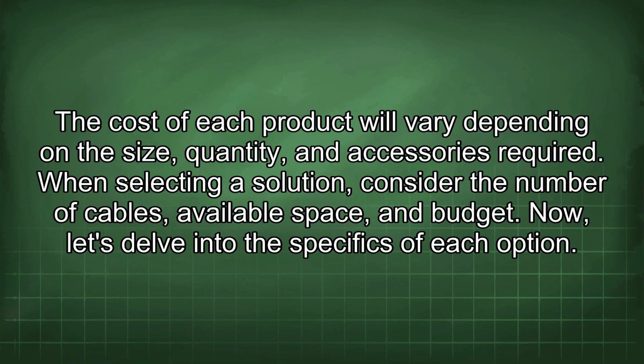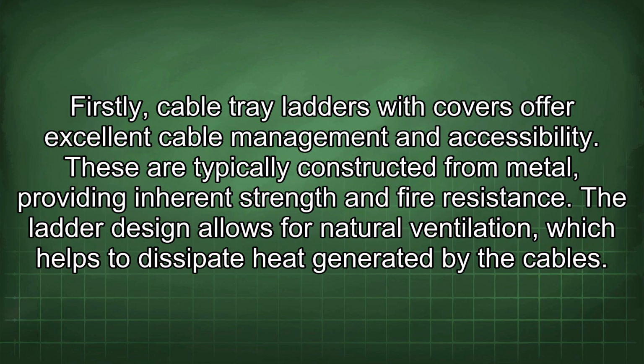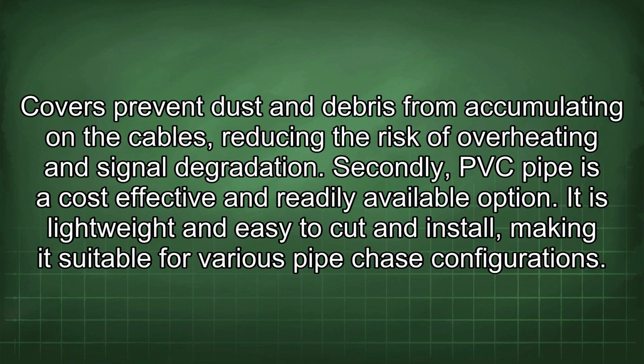The cost of each product will vary depending on the size, quantity, and accessories required. When selecting a solution, consider the number of cables, available space, and budget. Now let's delve into the specifics of each option. Firstly, cable tray ladders with covers offer excellent cable management and accessibility. These are typically constructed from metal, providing inherent strength and fire resistance. The ladder design allows for natural ventilation, which helps to dissipate heat generated by the cables. Covers prevent dust and debris from accumulating on the cables, reducing the risk of overheating and signal degradation.